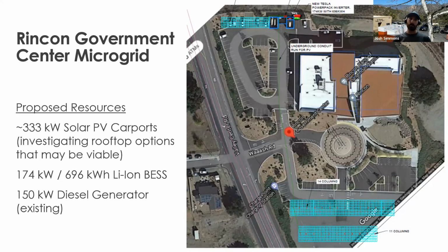Certainly, there are ways to streamline that and move it faster, but there are also supply chain considerations too. It's hopefully starting to ease up, but for some of these larger systems, switchgear, a major electrical component in these systems, has had a year of lead time to order. And you can't really order the switchgear until you've done some of the advanced engineering of the project and had sign off from the utility on the basic engineering of the system.